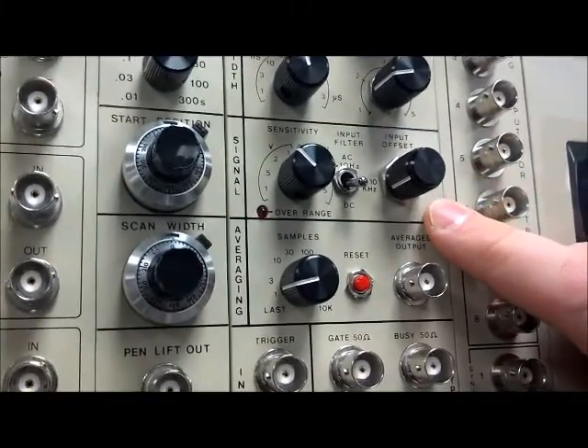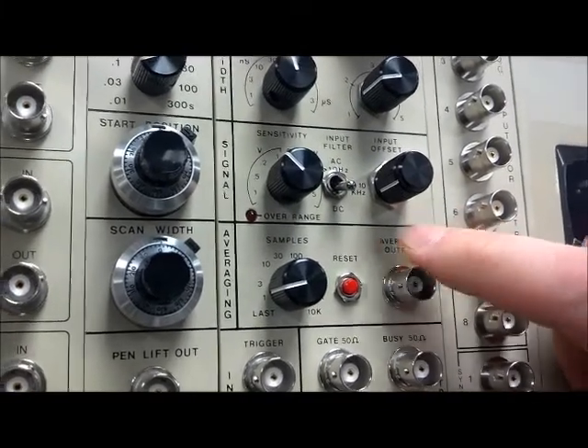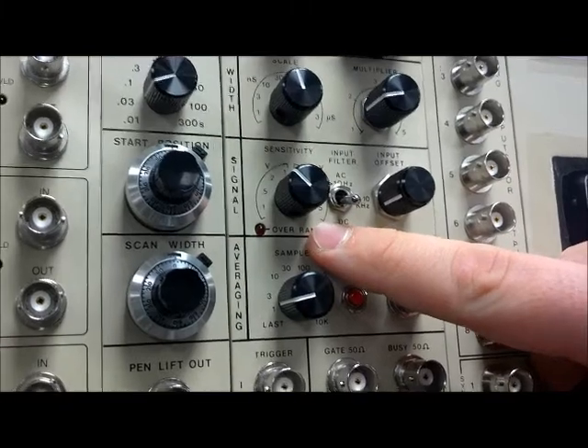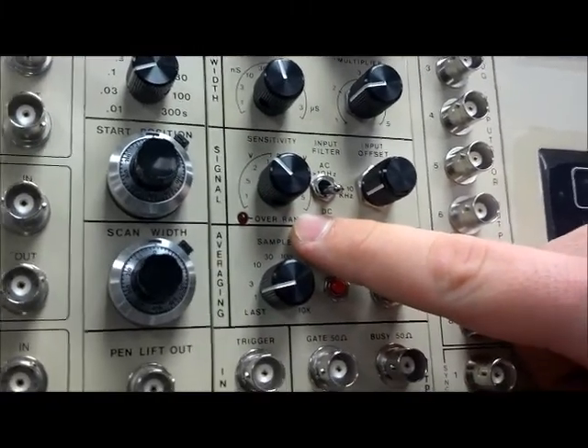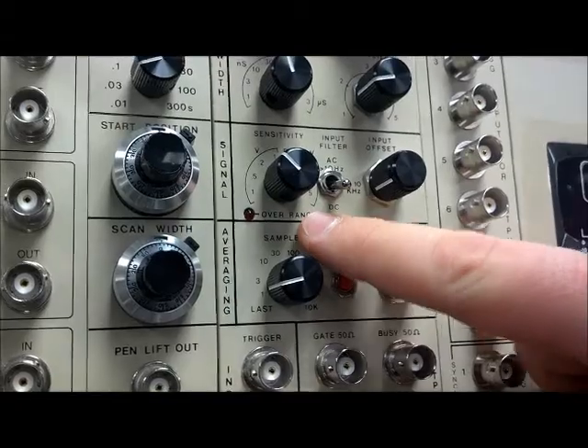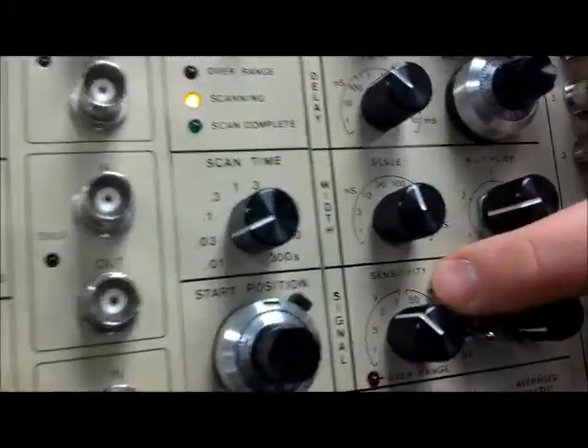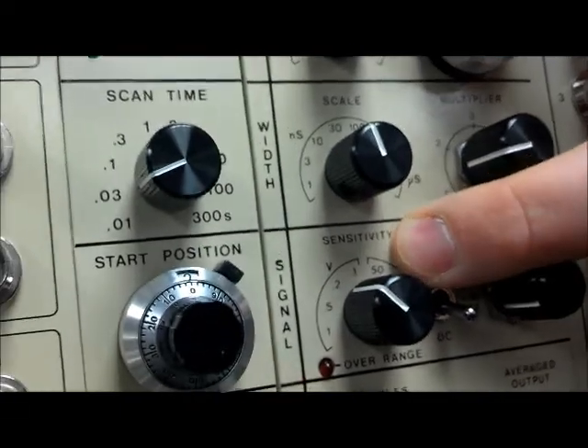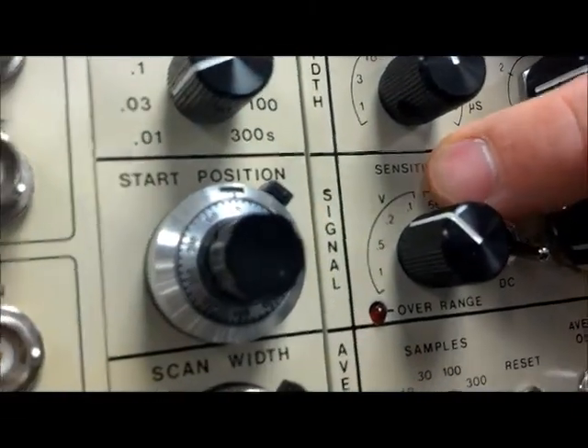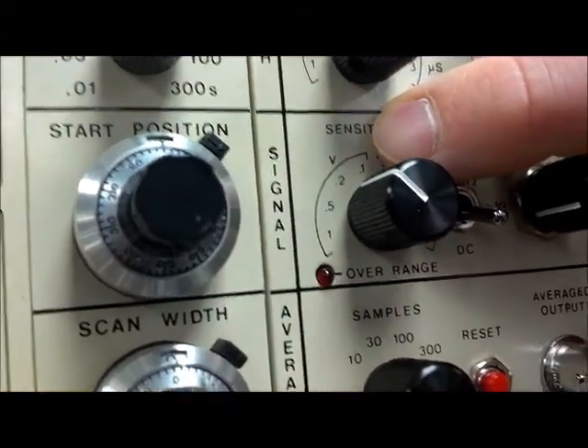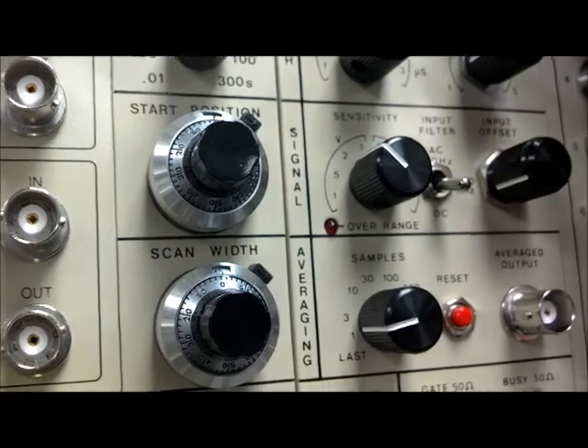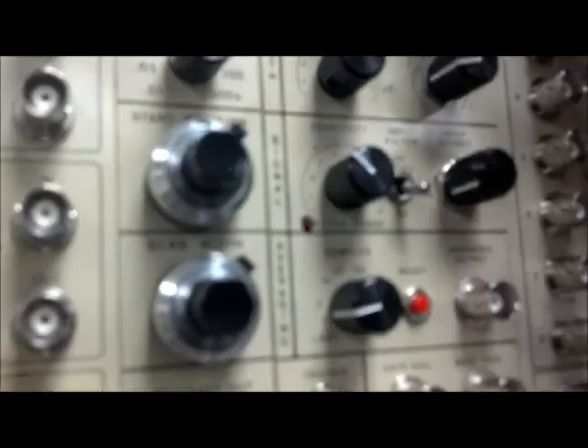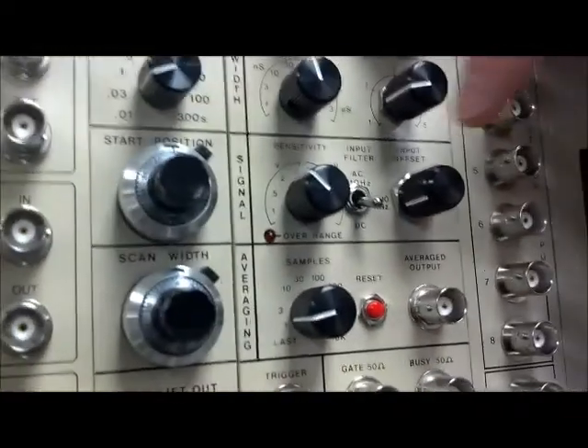Next is the signal section. In the signal section, the sensitivity of the output amplifier can be adjusted to multiply the output signal by a particular factor. For instance, right now the sensitivity is set to .2 volts per volt. So that means for every .2 volts into the amplifier, one volt gets put out. It's basically like a scaling multiplier of five.